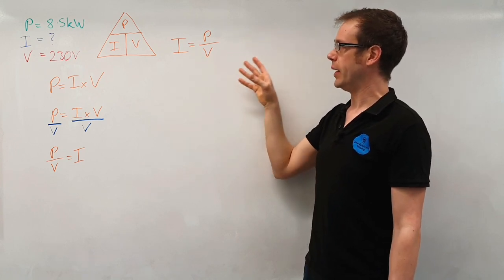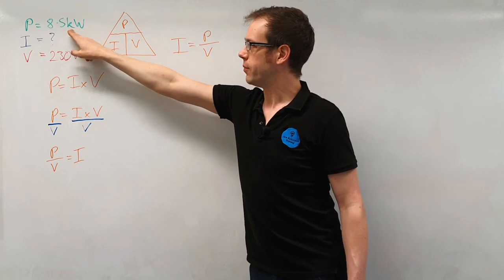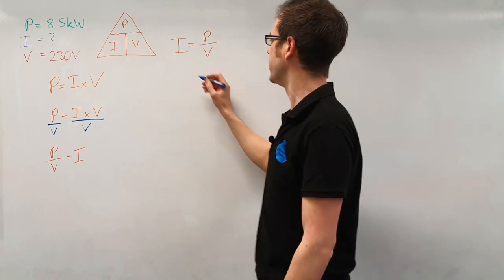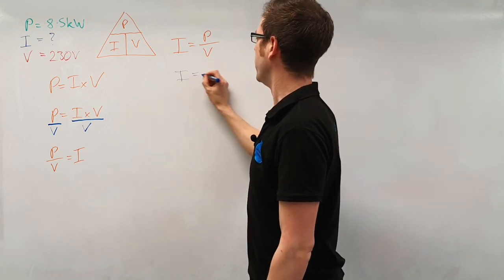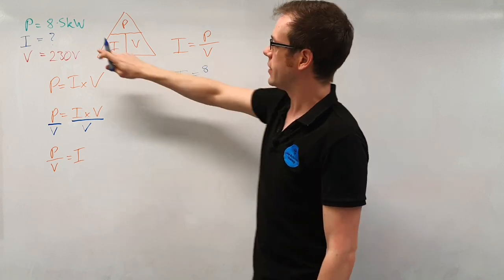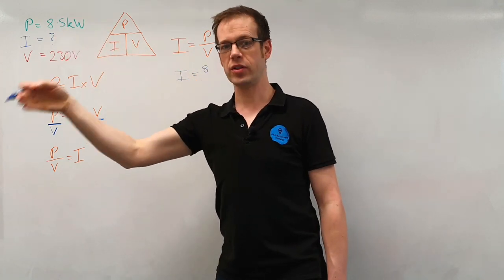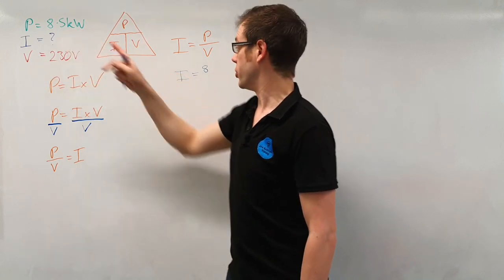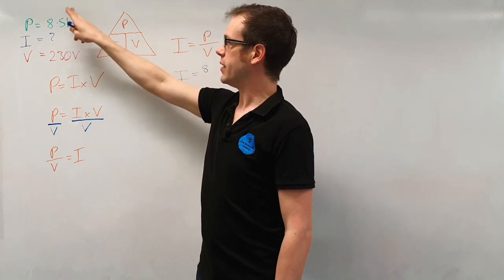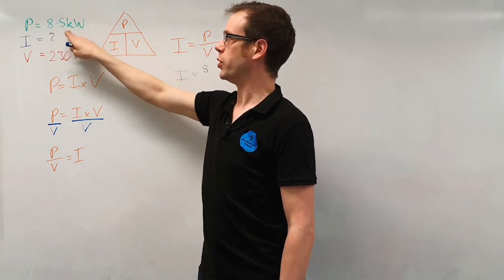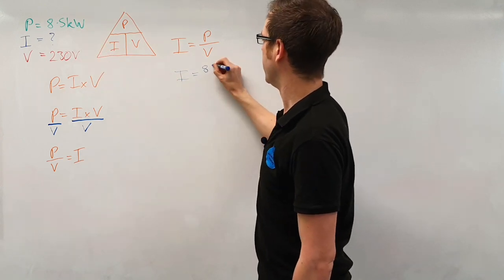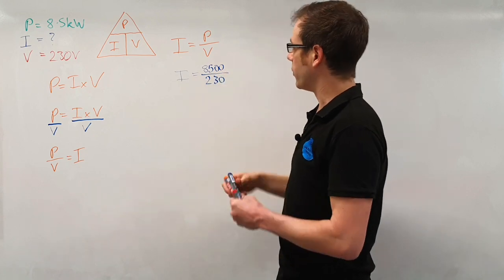Whichever way you do it we've got our formula I equals P over V. We know what P is, we know what V is, so the next thing we can do is just very simply put these values into our calculation. So we can say that I will be equal to 8.5 kilowatts. Now because this is 8.5 kilowatts, the kilo means thousand. You can swap that out for times 10 to the power of 3. That times 10 to the 3 means move the decimal point one, two, three spaces and it becomes eight thousand five hundred, divided by 230.